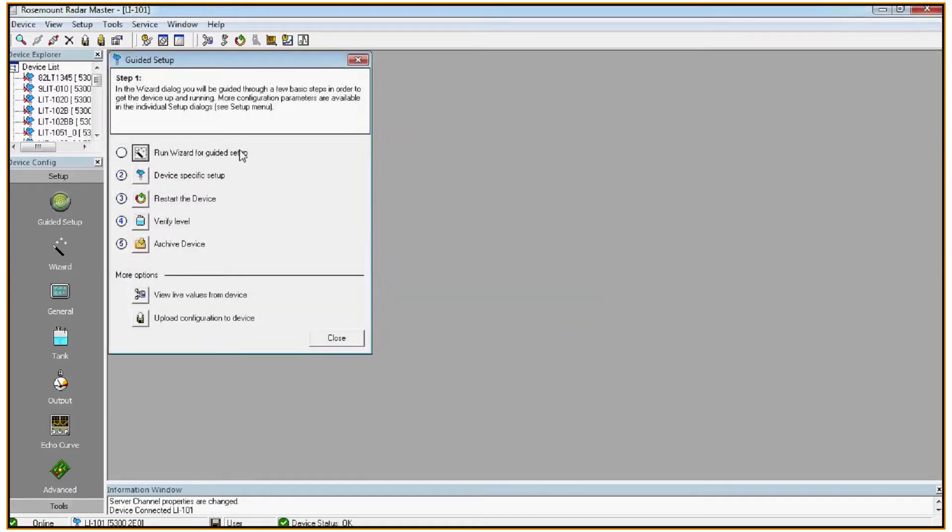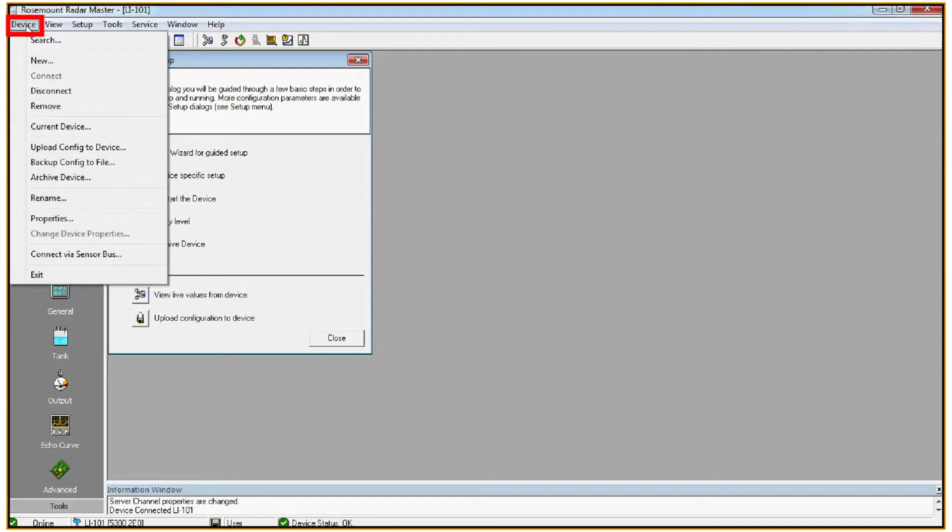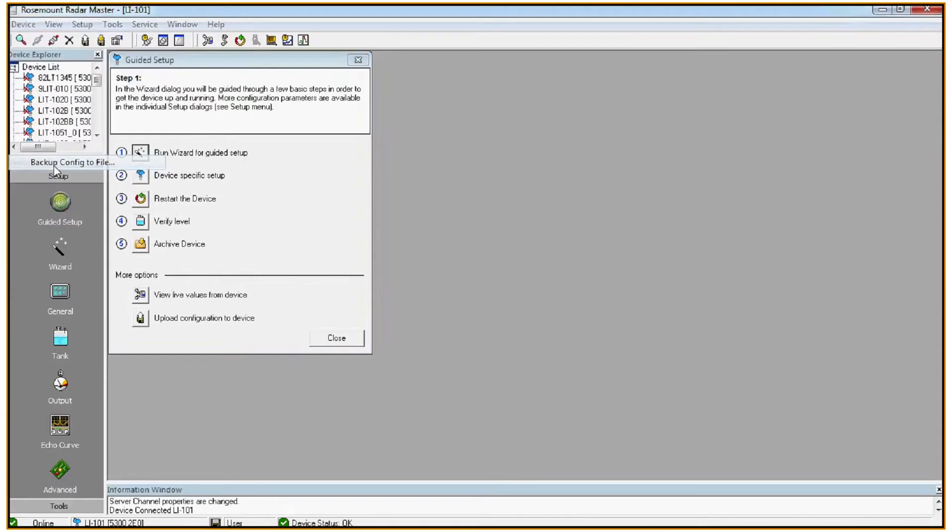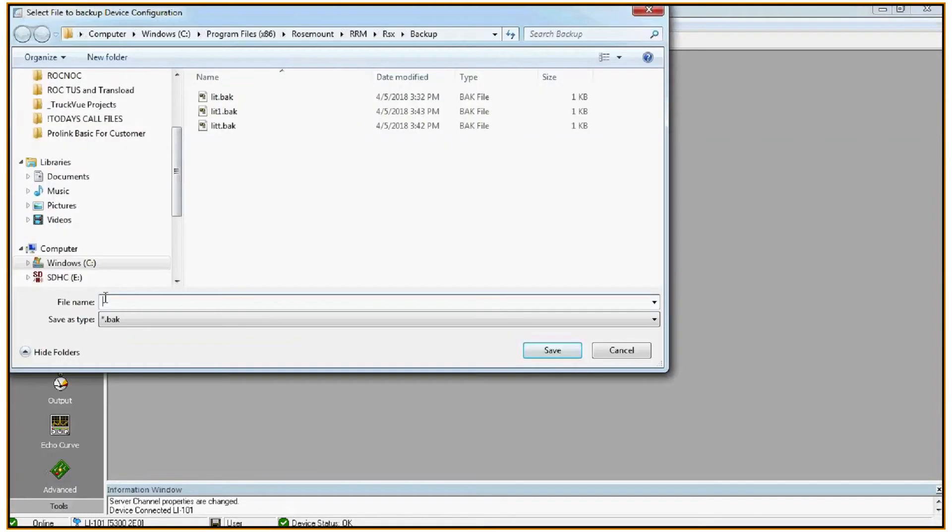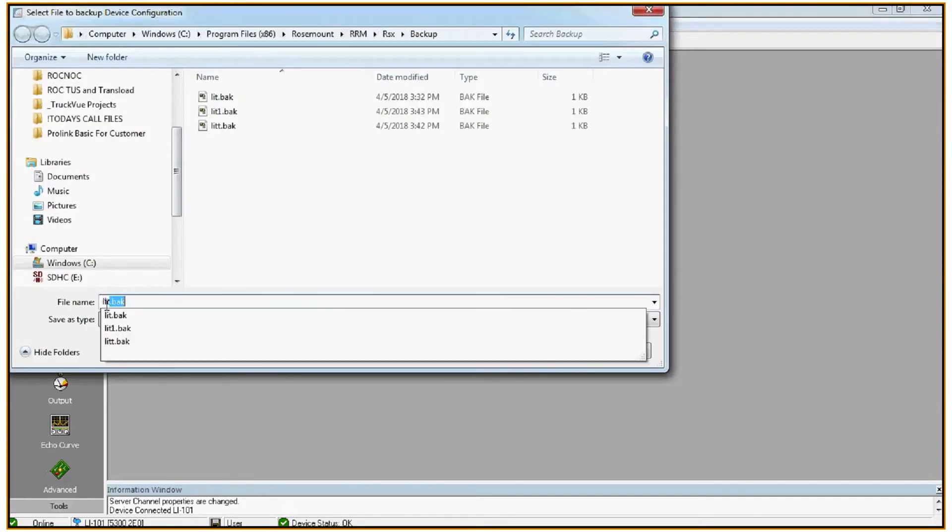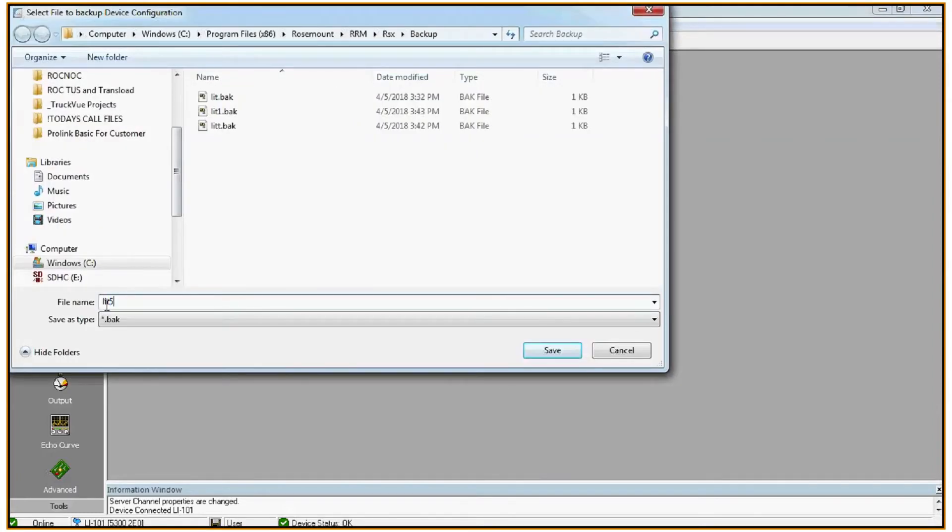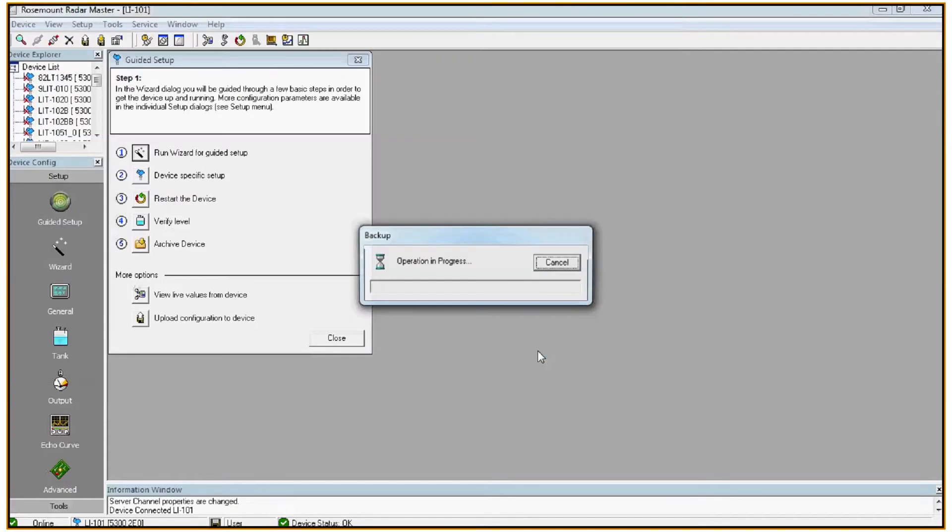Whenever you've connected to a device for the first time, it's always a good idea to save an as-found configuration. To do that, click on device in the top left corner, select backup config to file. Give the backup a name that you'll remember and make sure it's saved somewhere that you can recall later. Click save and the file will be backed up.